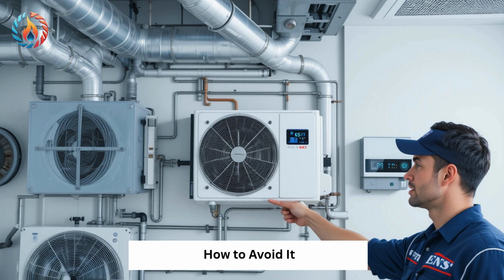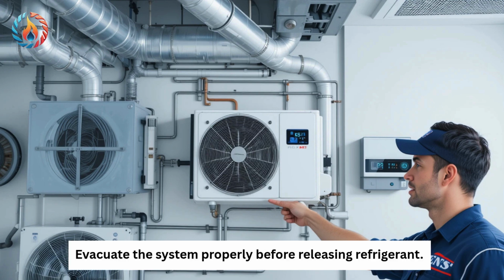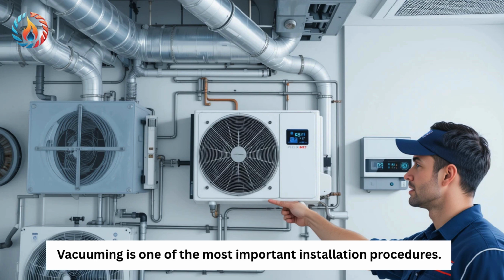How to avoid it? Always use a vacuum pump. Connect a manifold gauge set, and evacuate the system properly before releasing refrigerant. Vacuuming is one of the most important installation procedures.